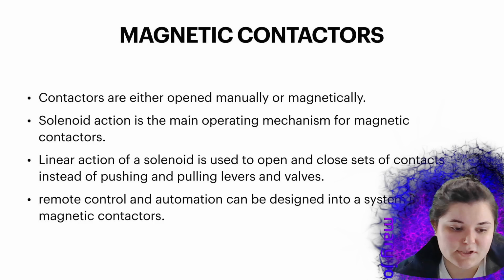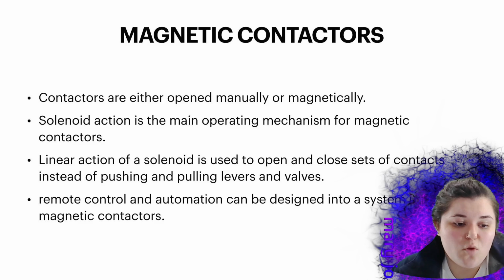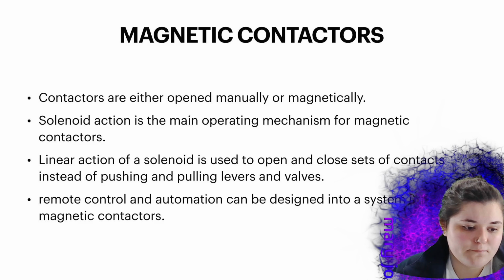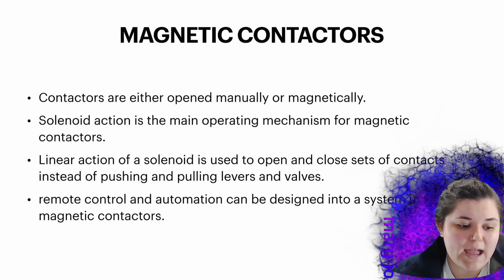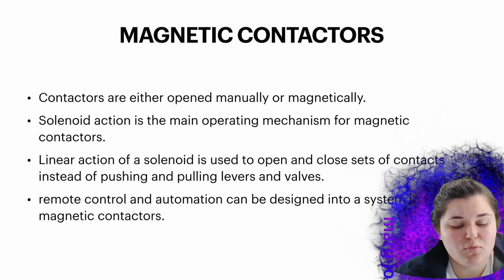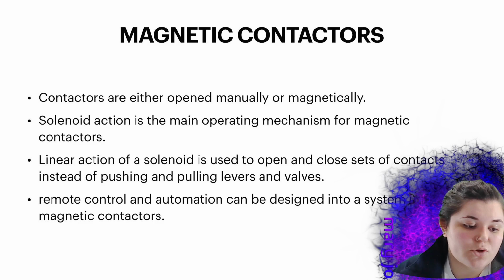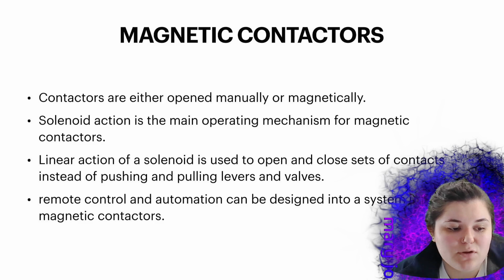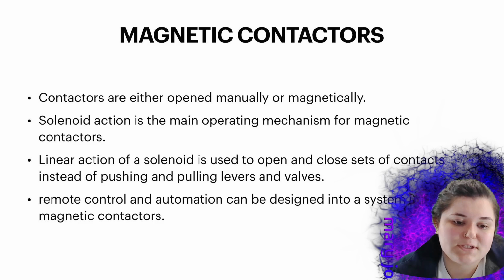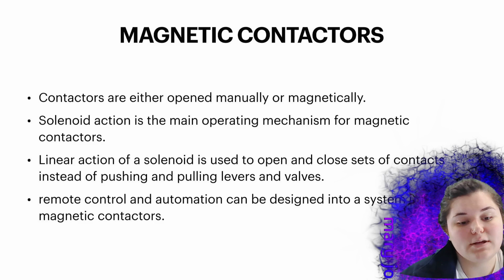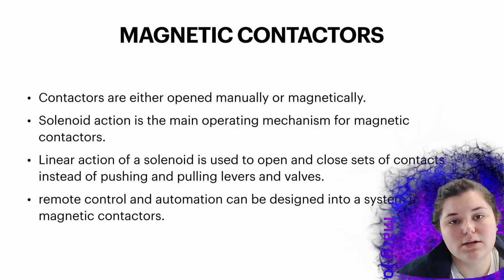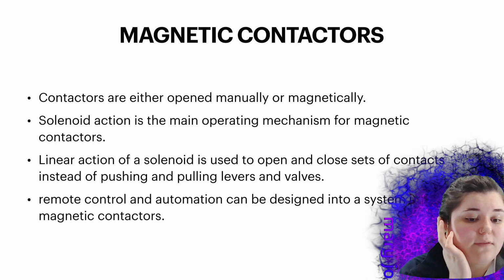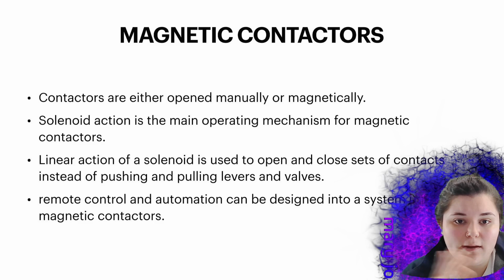Magnetic contactors. Contactors are either opened manually or magnetically. Solenoid action is the main operating mechanism for magnetic contactors. Linear action of a solenoid is used to open and close sets of contacts instead of pushing and pulling levers and valves. Remote control and automation can be designed into a system using magnetic contactors. Little side note, contactors have either an AC or DC coil, not both, but could have either AC or DC contacts.